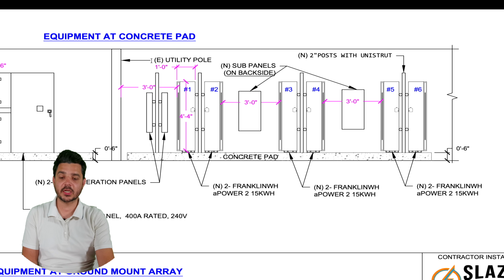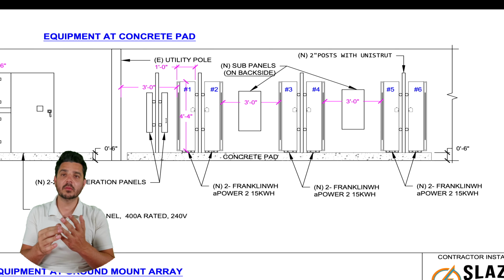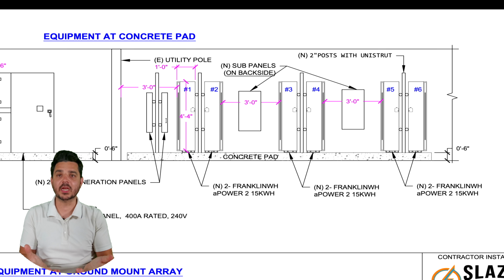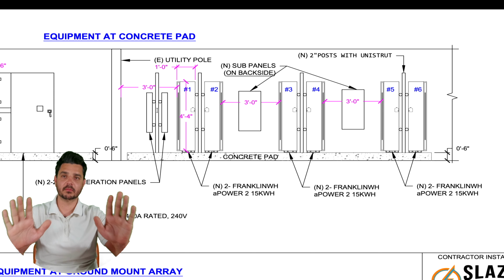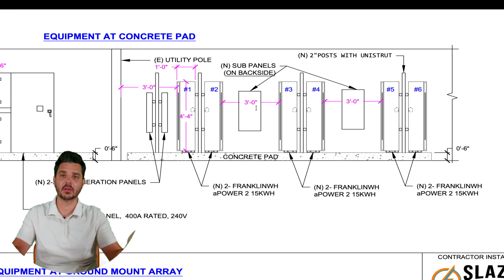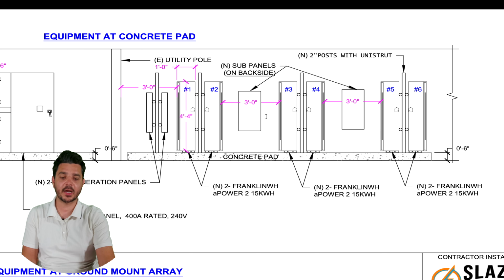Another change is with the sub panels combining the aPower units. We're combining 3 aPowers together then going to each aGate, so we need a sub panel for that. We originally planned to put the sub panels here, but it's better to place them parallel against the wall, further back, so they don't block anything. That allows us to come out of the Franklins, go under, and come back up. These will be on 2-inch posts with unistrut going across, with 4, 5, 6 on this sub panel and 1, 2, 3 on the other, each going to their appropriate aGate.